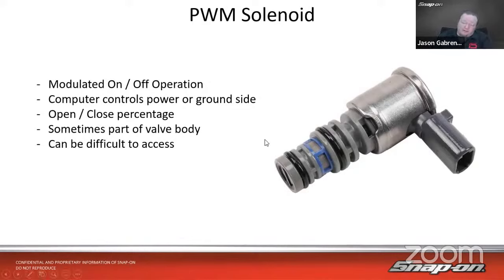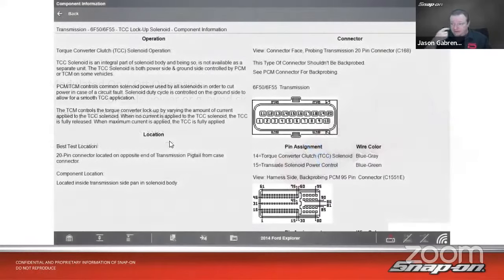So we would look at pulse width modulated. In that case, some manufacturers use just these, some manufacturers use a mixture of on-off and pulse width modulated. And if it is part of the valve body, once again, can be difficult to access.